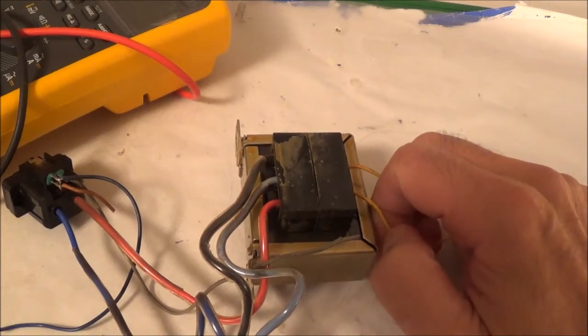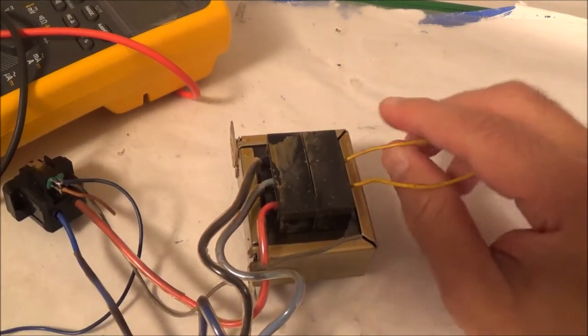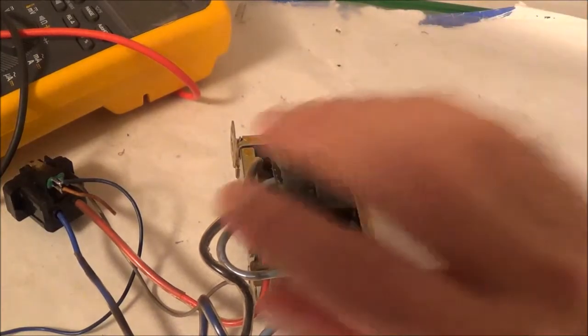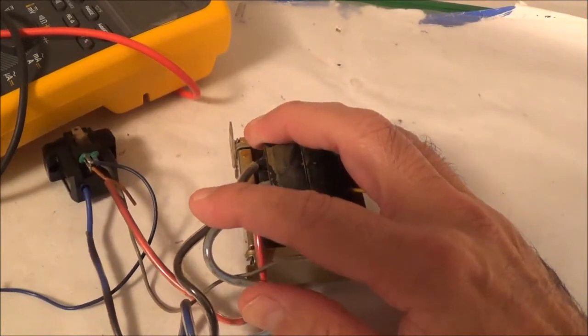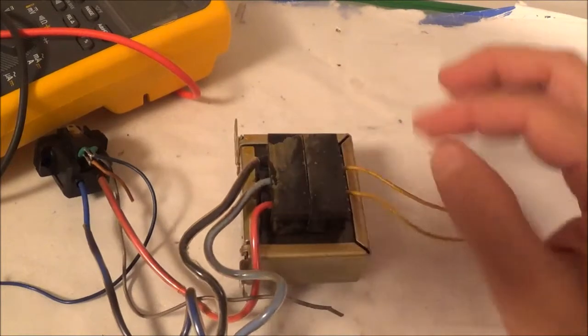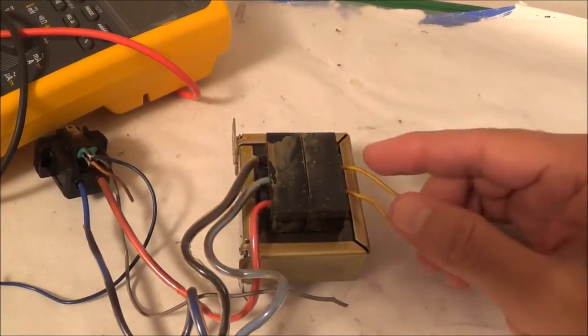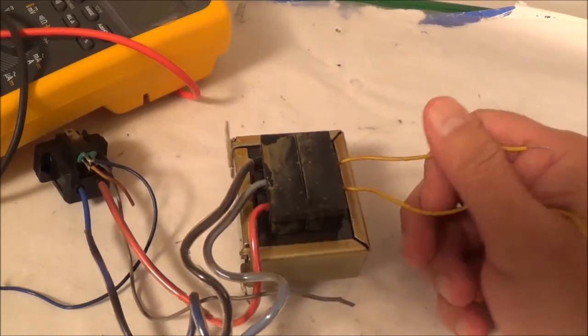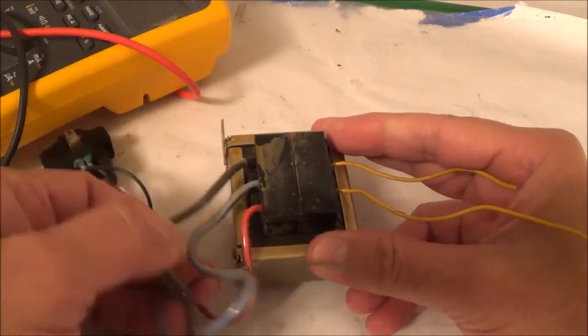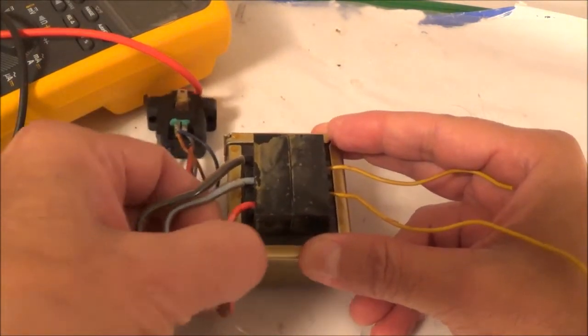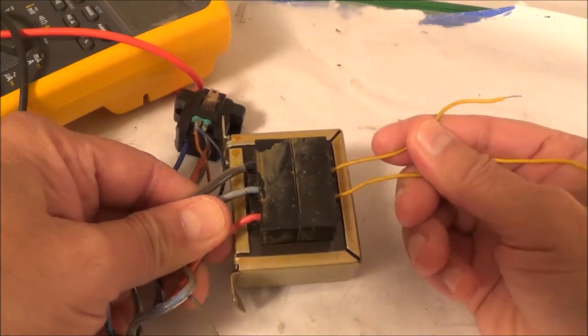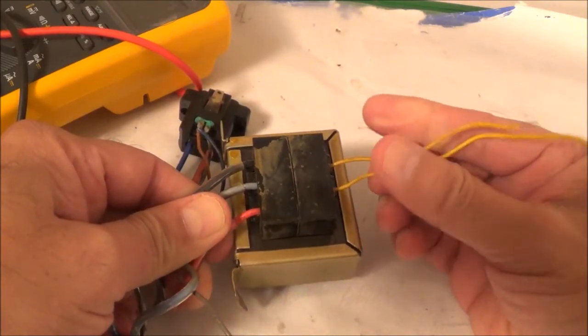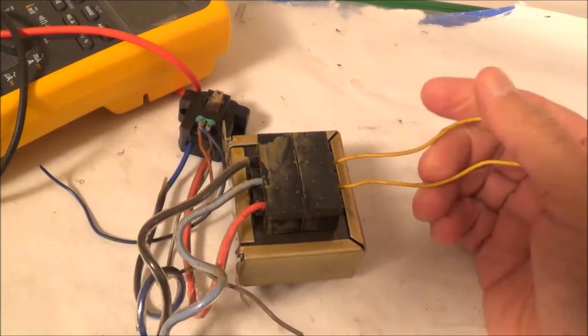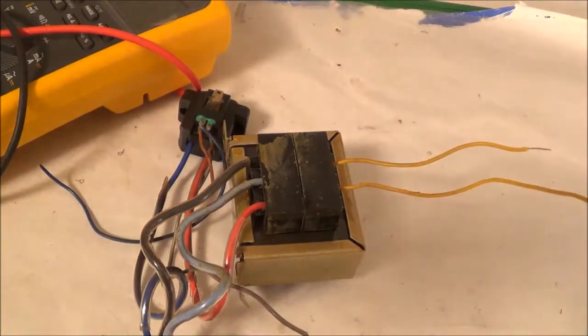This can't be done by measuring the resistance. Say if I measure the resistance on the primary side and the secondary side, that's not going to work. Some people do think that'll give you the turns ratio, but that alone won't. You can already tell by the different thicknesses of the wire that they're going to have different resistance, so that's not an approach you can take.